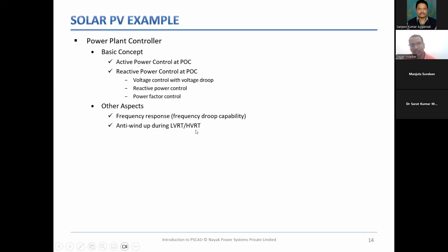Already discussed frequency response. Apart from that, you also have something called anti-windup during LVRT, HVRT events. As I said, LVRT, HVRT is not the responsibility of the PPC, but rather of the converter, because it is a fast behaving device. But the PPC should take some decision, right? Either to supply additional reactive power support during an LVRT event to clear the fault, or it should freeze. Typically, it takes one of the two decisions. Most PPCs freeze the P and Q order during LVRT and HVRT events.